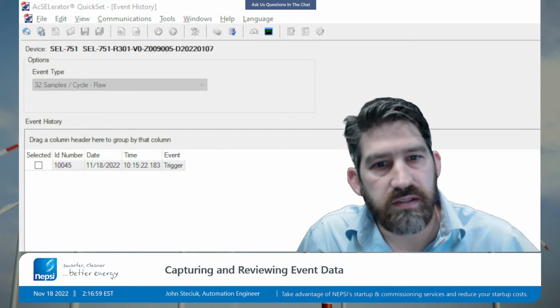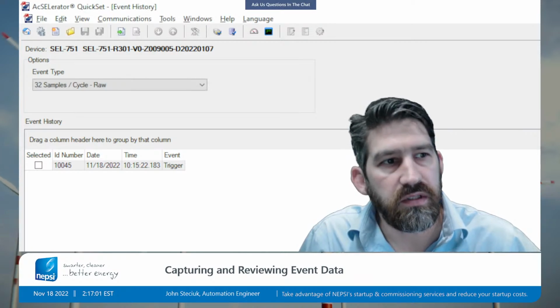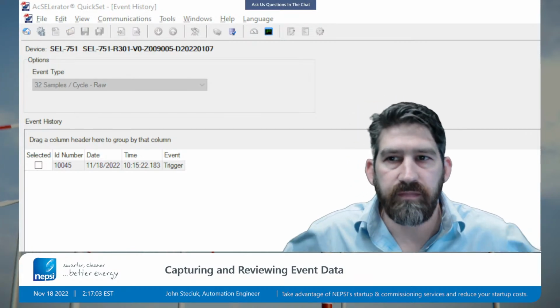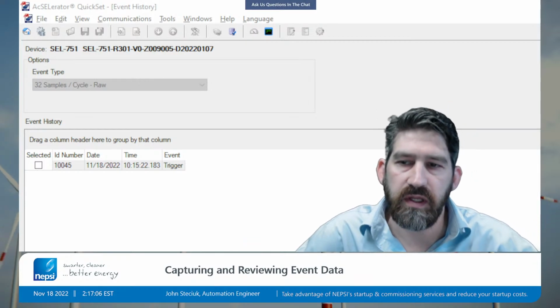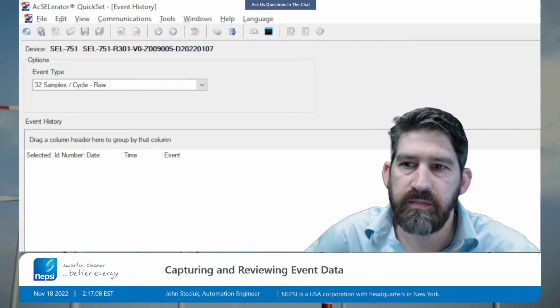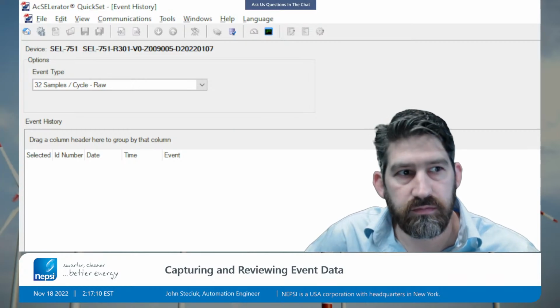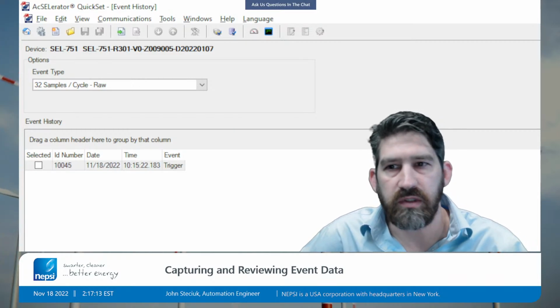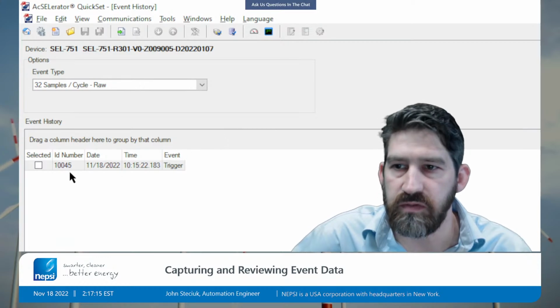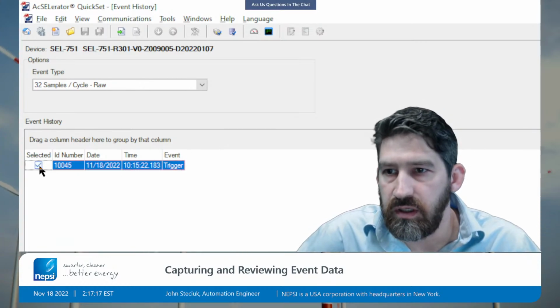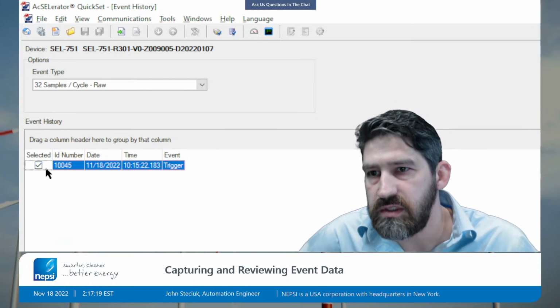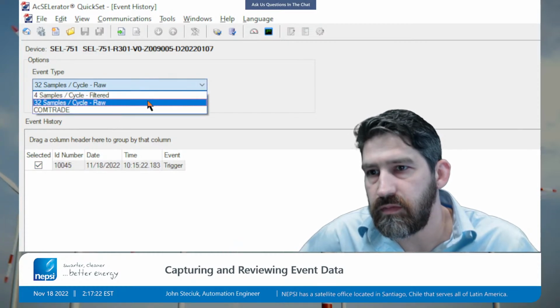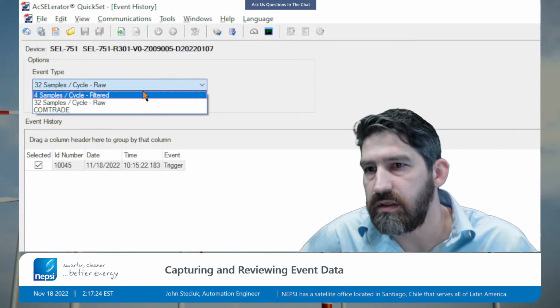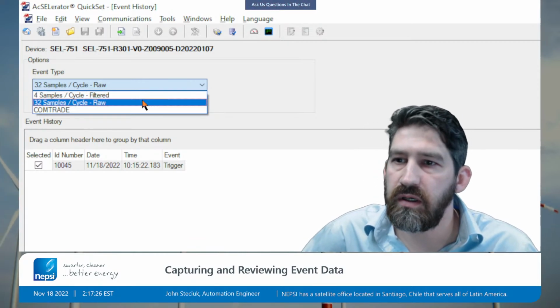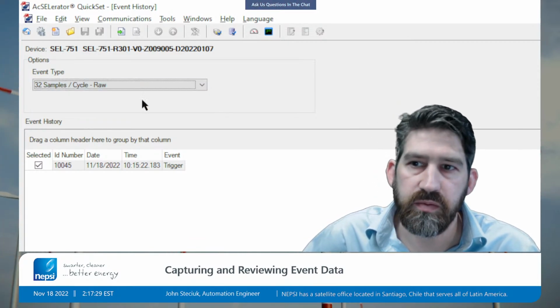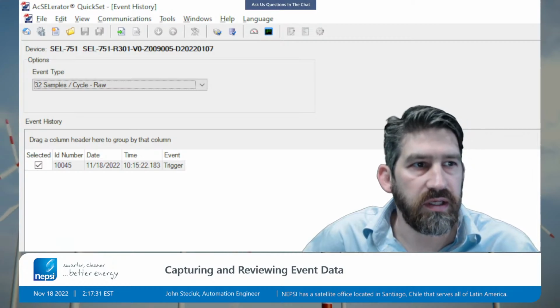It's going to go to the relay and find any events that are in the relay's memory. And that takes just a moment to get the information from the relay. Then you can select the event report that you want and also the type of file you want. I'm going to choose the 32 samples per cycle and click Get Selected Events.